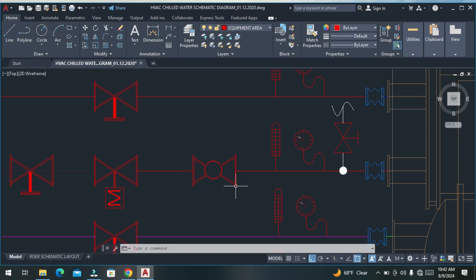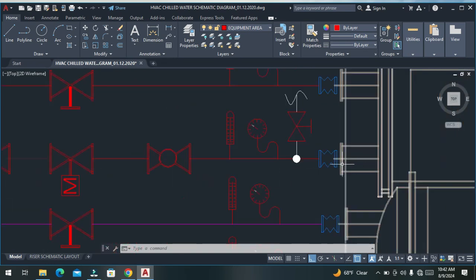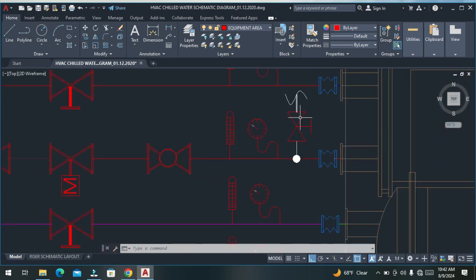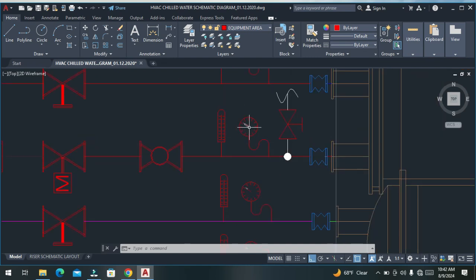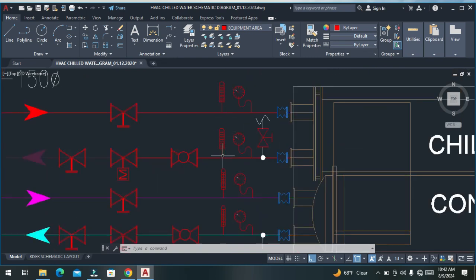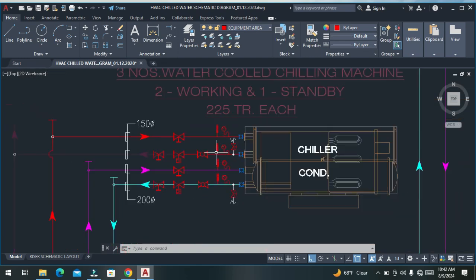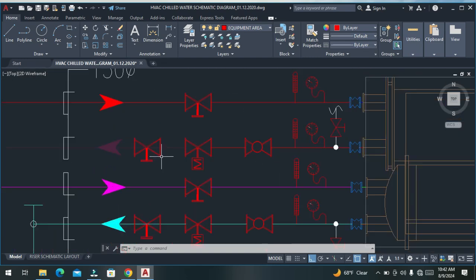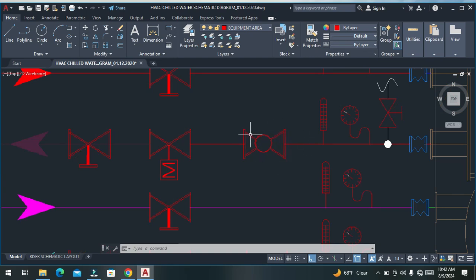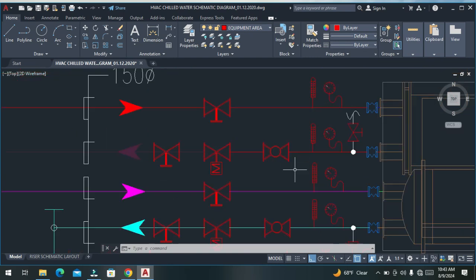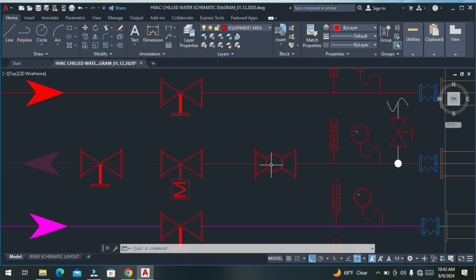If you talk about the components in the pipeline, this is the drain point, and then we have a pressure gauge meter. We can observe the pressure of this water supply line, and this is the thermometer, where we can observe the temperature of this outgoing evaporator line. Then this is the balancing valve, which actually helps us during water balancing.